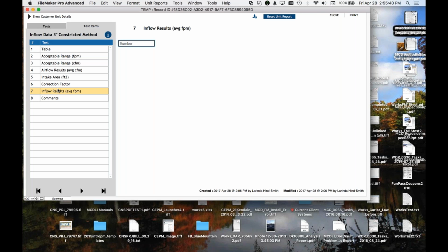Yeah, the inflow results, there's a grid on the report that fills the page left to right, and then below it three individual gridded sections that have the different methods. Like the direct inflow method, the exhaust filter, I don't remember the exact wording, the exhaust filter method and the constrictor method. Those are the summary of the results. Oh, it says direct inflow, exhaust grid, and constricted access.